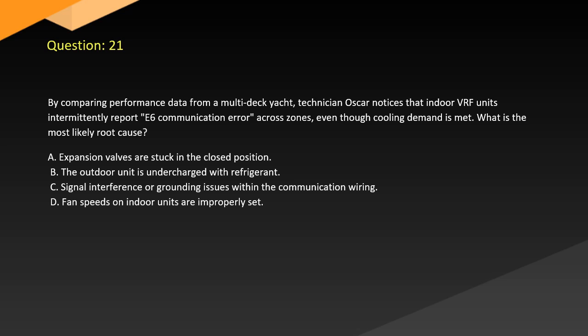Question 21. By comparing performance data from a multi-deck yacht, technician Oscar notices that indoor VRF units intermittently report communication errors across zones even though cooling demand is met. What is the most likely root cause? A. Expansion valves are stuck in the closed position. B. The outdoor unit is undercharged with refrigerant. C. Signal interference or grounding issues within the communication wiring. D. Fan speeds on indoor units are improperly set.